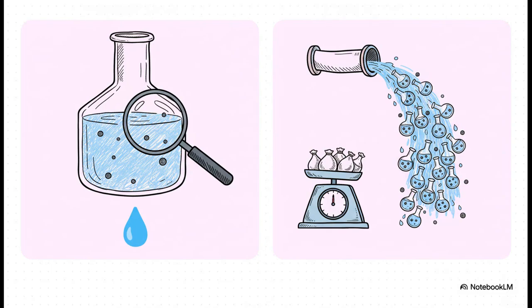It's especially critical when it comes to following the rules. A permit might have a concentration limit, saying your water can't be stronger than 30 milligrams per liter. But it will also have a mass limit, saying you can't discharge more than, say, 5,000 pounds of that pollutant per day. Now, you could have really clean water with a low concentration, but if you're discharging a massive volume of it, you could still break that mass limit. You have to use the Pounds formula to know for sure.